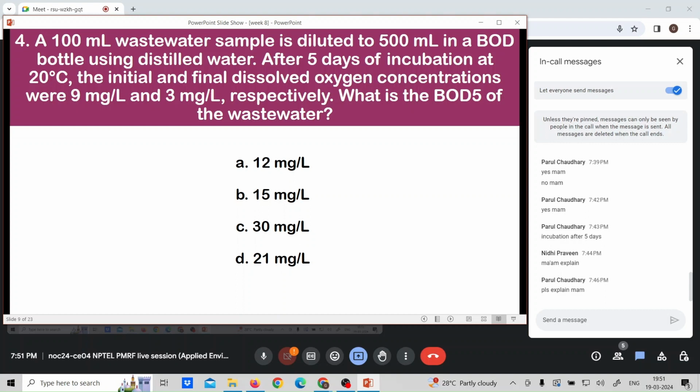One more explanation: generally in all parts of the world we have this habit of finding out the BOD after 5 days. That is because of the fluctuations in the dissolved oxygen concentration. When you leave it for so many days, sometimes it may happen that you seal the bottle tightly, so all your dissolved oxygen may get exhausted. That will also show you an erroneous result.